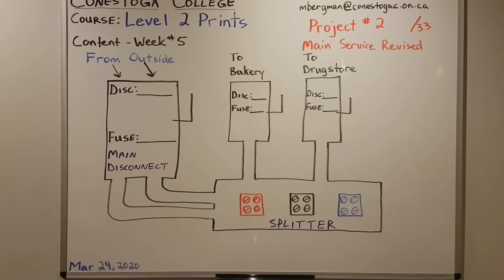Once we get into the units, we're going to go into a transformer on the primary. We're going to leave the secondary of the transformer and go into another disconnect, which will be fused. That's 120/208 now, so we've established our neutral. We've grounded our transformer. From that disconnect, we then head into our panel, and we're now ready to distribute circuits throughout the units.